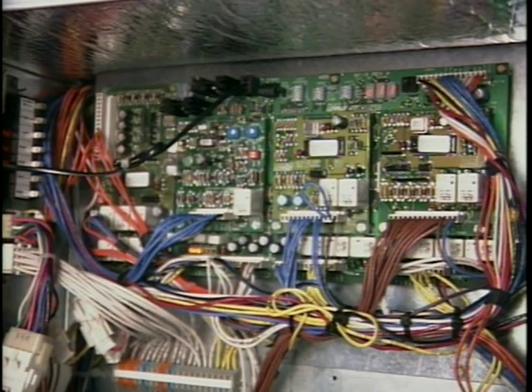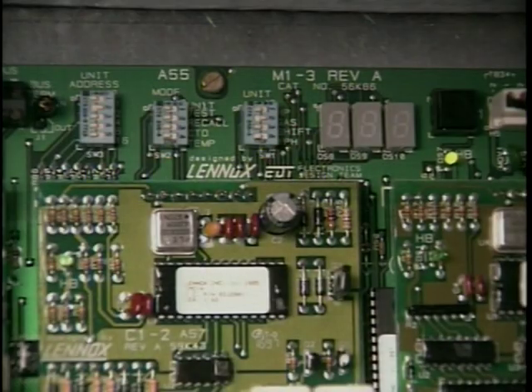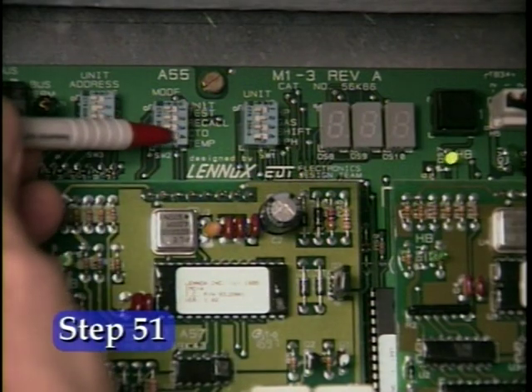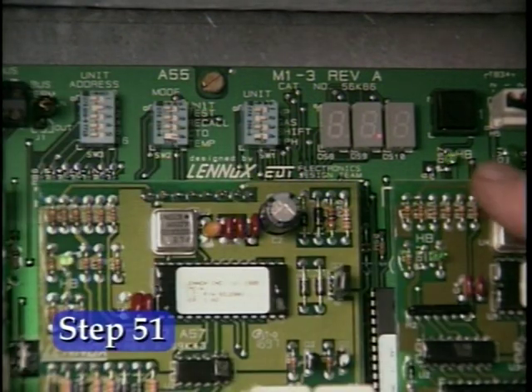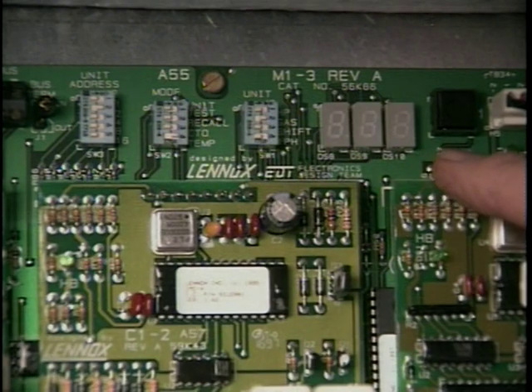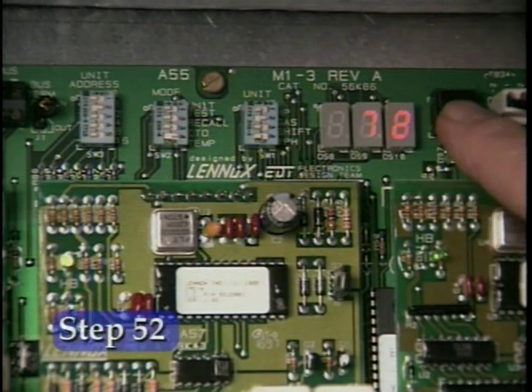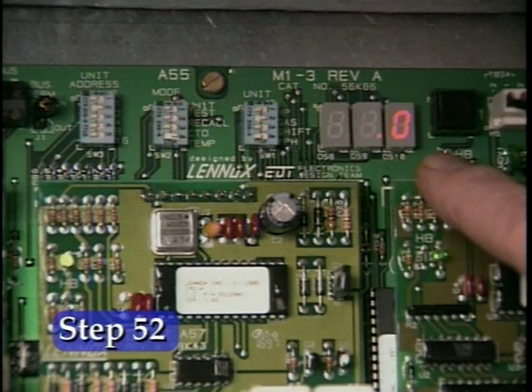The temperatures must be read and recorded within 60 seconds of turning the fan and compressors off. Place switch 4 on SW2 on. The LED readout will alternate between point 0 and the ambient air temperature. Record the ambient air temperature in space 51. Press the display push button once to advance to point 1.